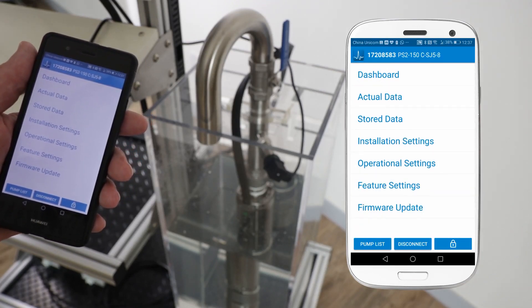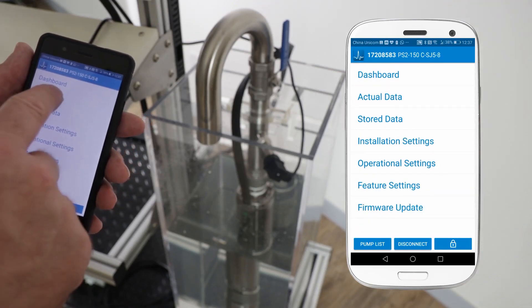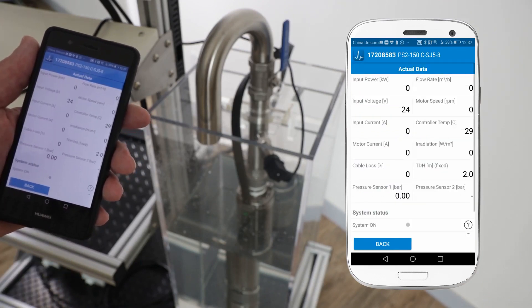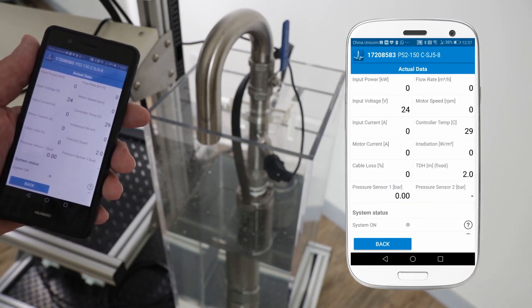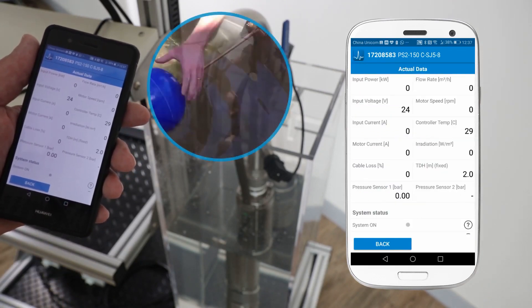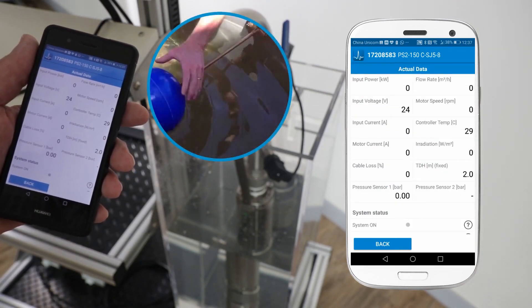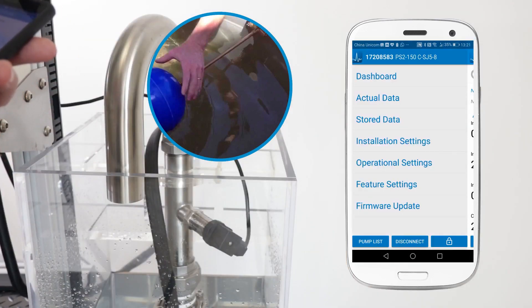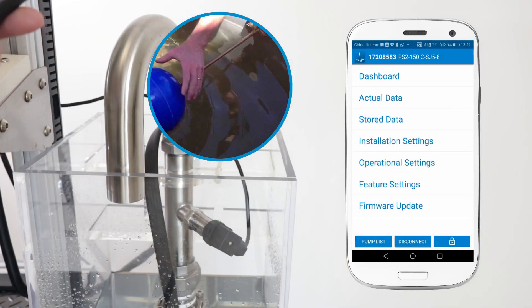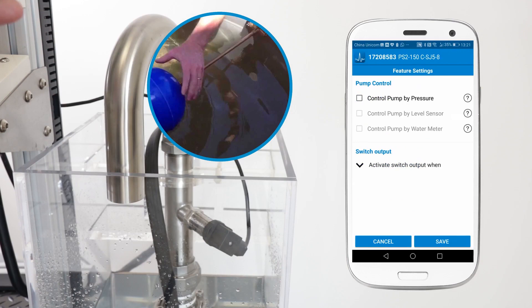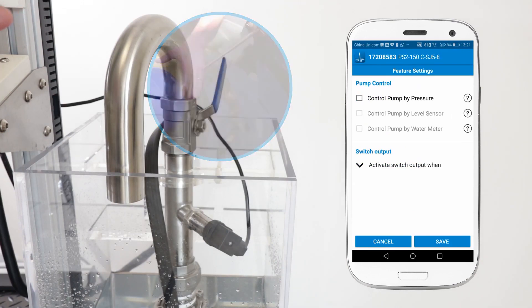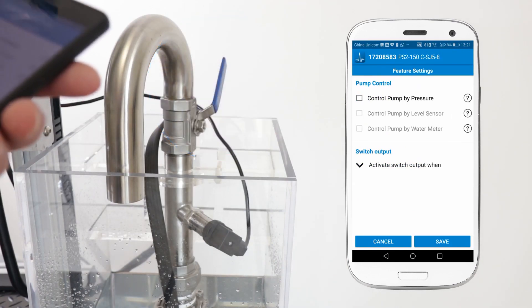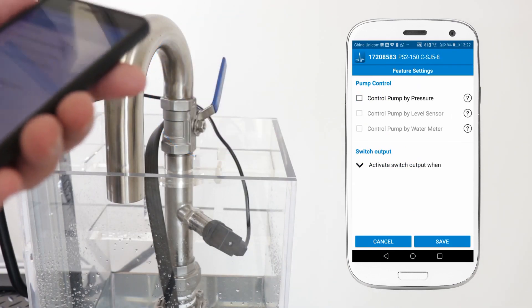So let's imagine now that we want to control the water going to a remote tank. What we can do is add a float valve to the tank that will close when the tank's full. The behavior we expect is the pump will pump water along the pipe. As the valve closes pressure in the pipe will rise and at that point we want to switch off the pump.